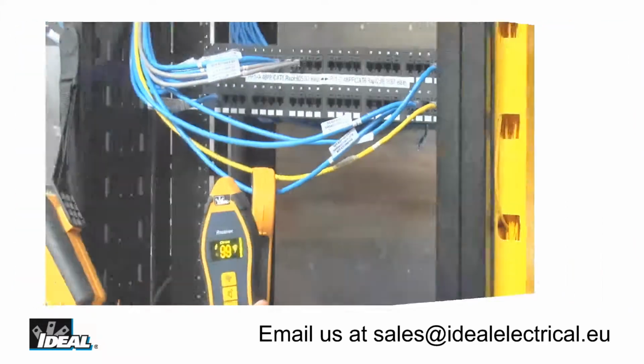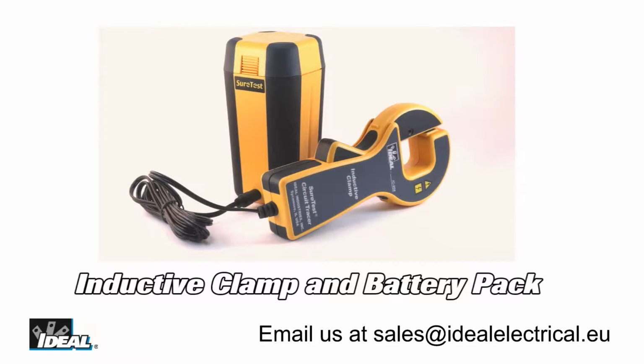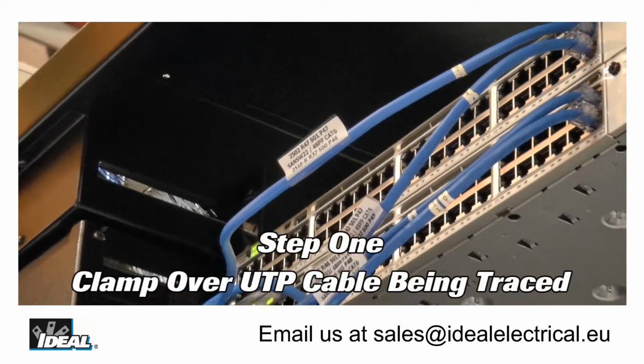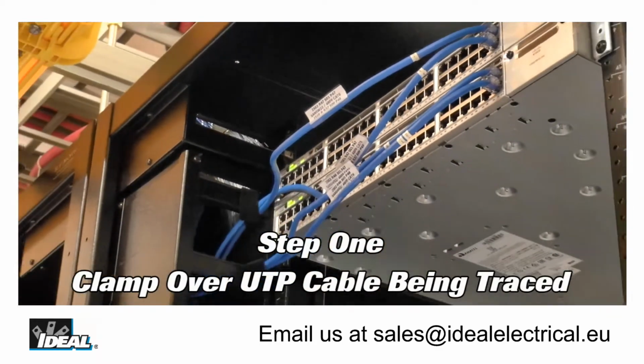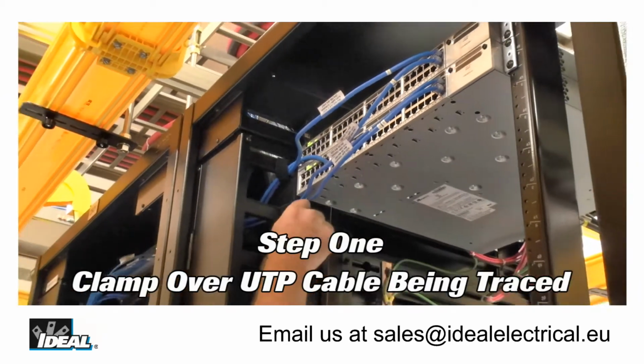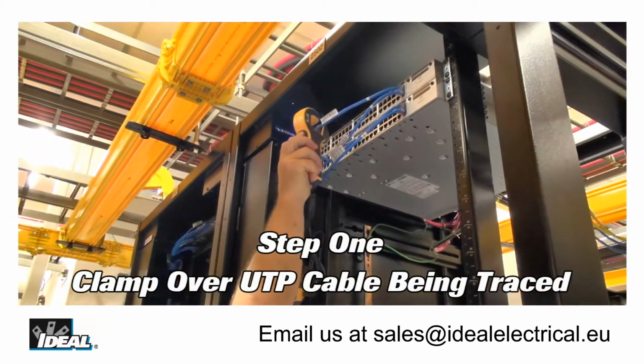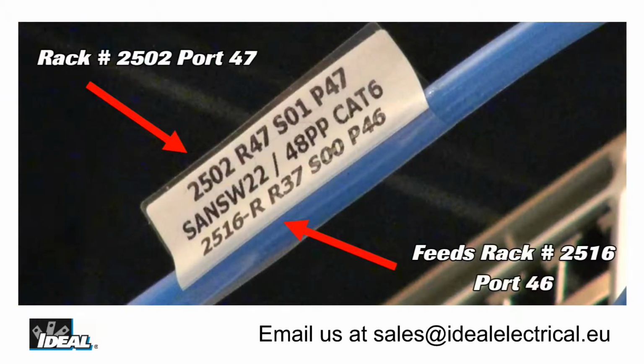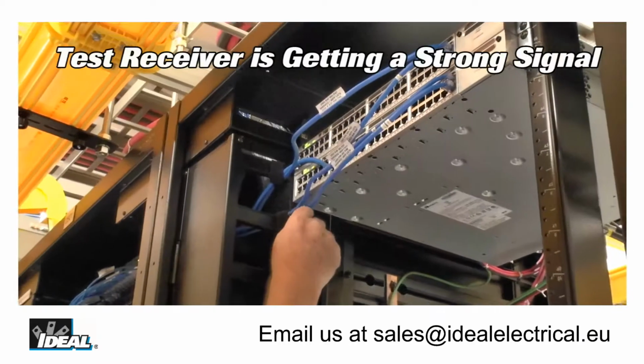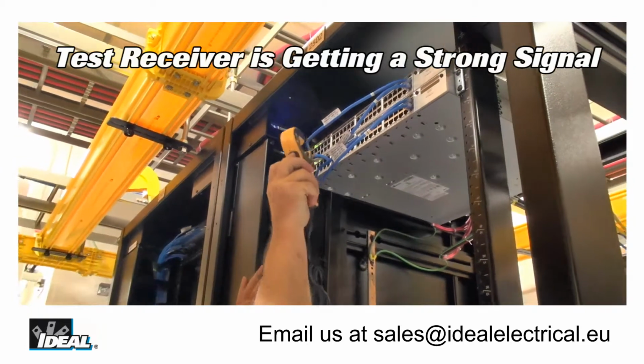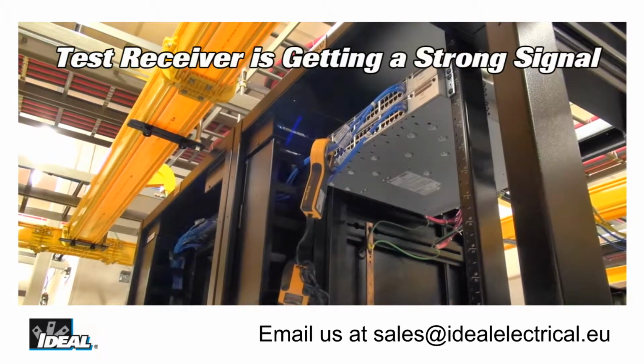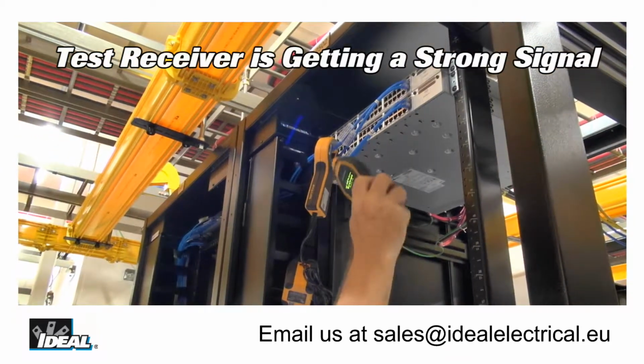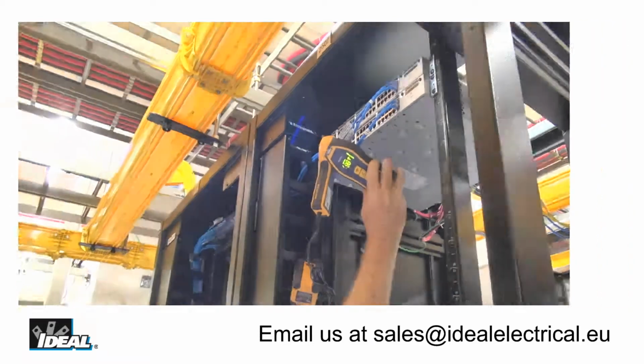traveling in the cable. Step 1 is to plug the inductive clamp into the battery pack and clamp over the cable being traced at the first rack, which is number 2502 in this case. From the label, we know the other end of the cable is in rack number 2516. Using the magnetic strap, hang the battery pack to the rack, then turn on the receiver unit and verify it is getting a strong signal from the transmitter.